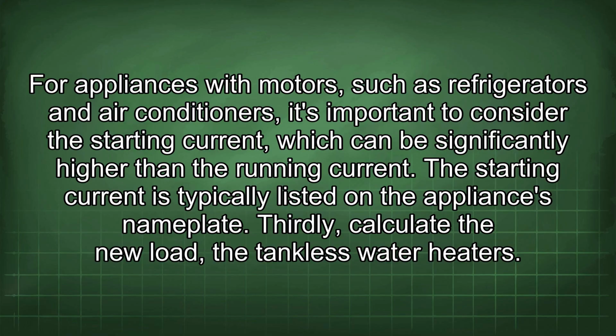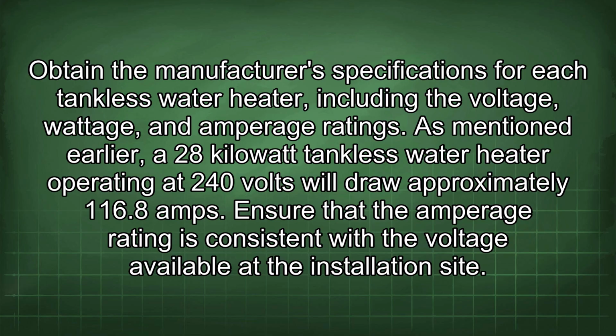Thirdly, calculate the new load, the tankless water heaters. Obtain the manufacturer's specifications for each tankless water heater, including the voltage, wattage, and amperage ratings. As mentioned earlier, a 28 kilowatt tankless water heater operating at 240 volts will draw approximately 116.8 amps. Ensure that the amperage rating is consistent with the voltage available at the installation site.